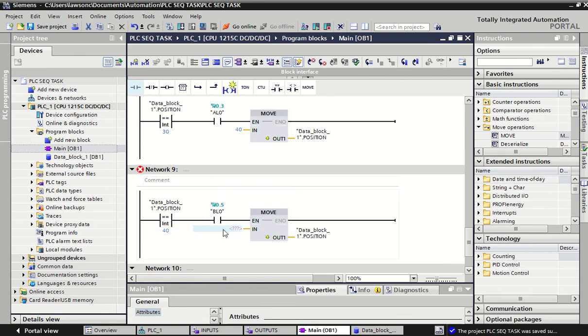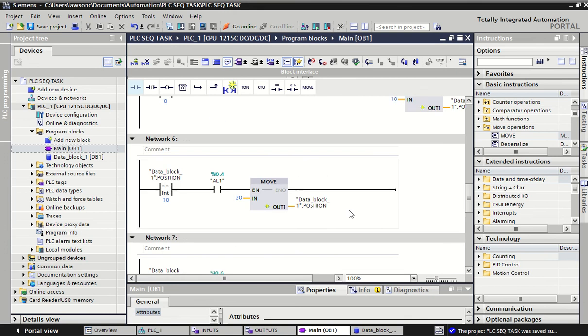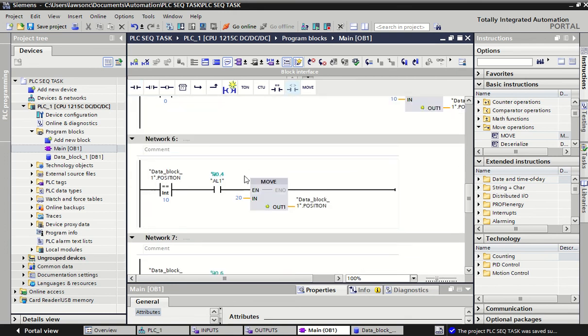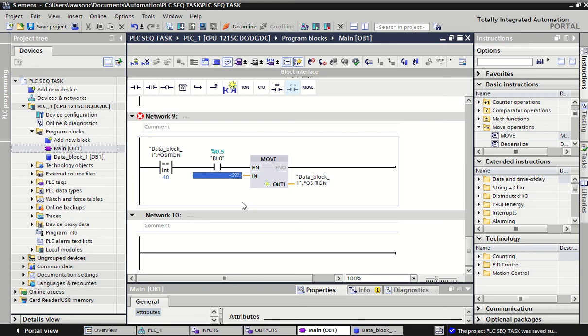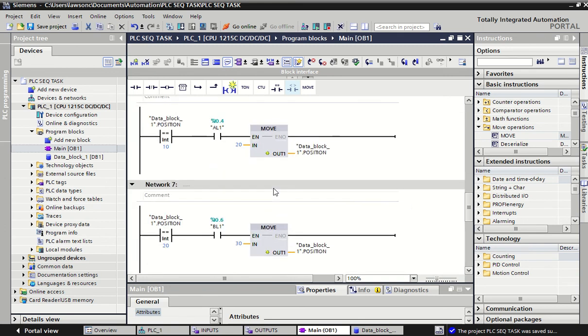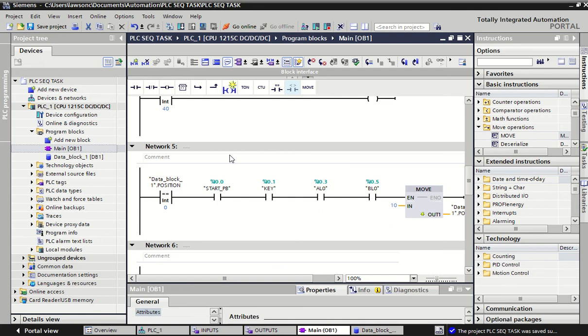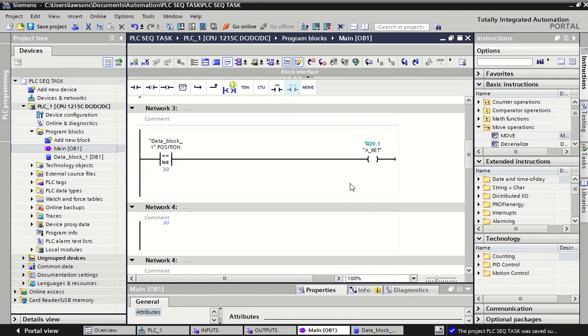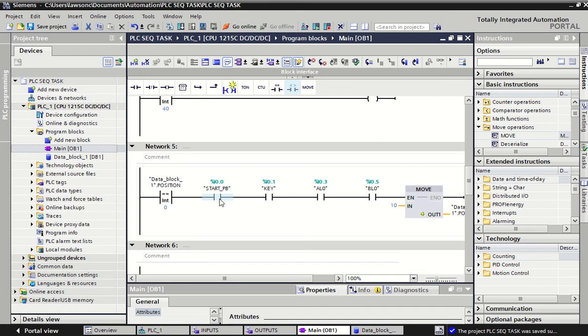Now the final thing to do is, well, what do I move to next? Well, if I move to step 50, I'm just going to be stuck in step 50. No outputs are going to happen and nothing will continue any further. So really I want this system to be repeatable. So what I want to do is move back to step 0, which will bring me back up to here. All the outputs will be off because nowhere does it say equal to 0 do something. But then we're up here and I'll wait for the start button to be pressed and the key to be turned, and they should be back in position and we can start it again.